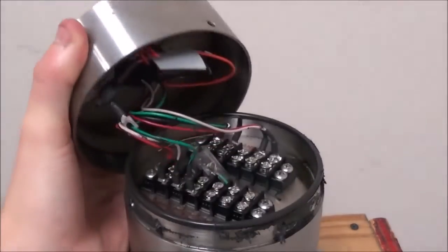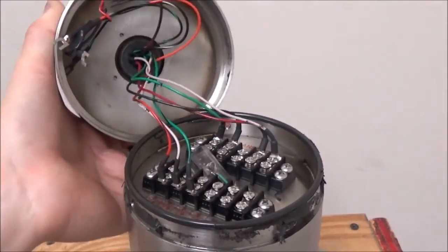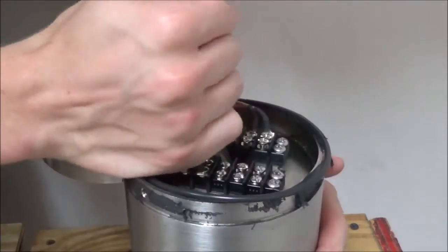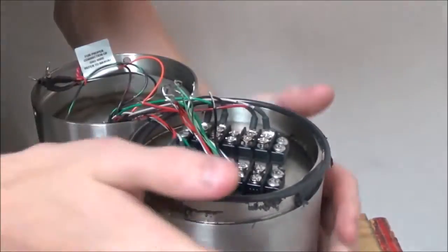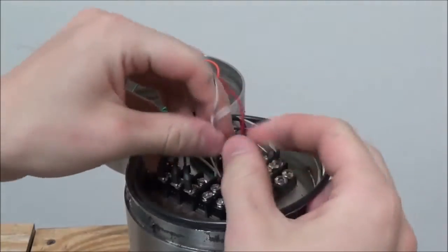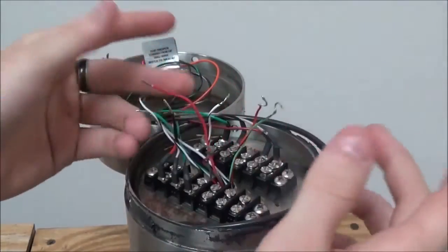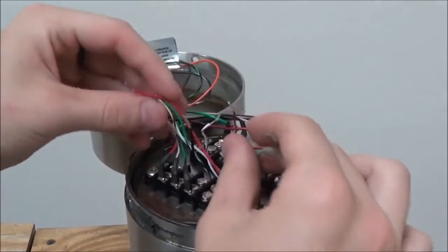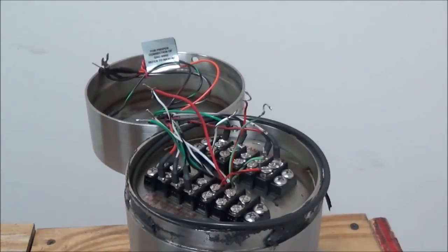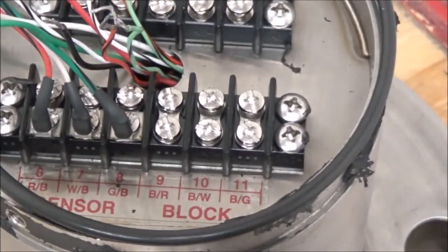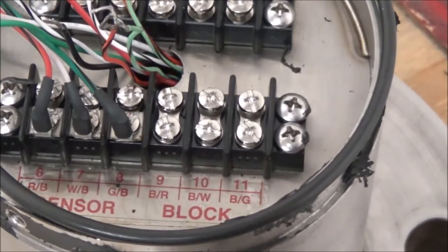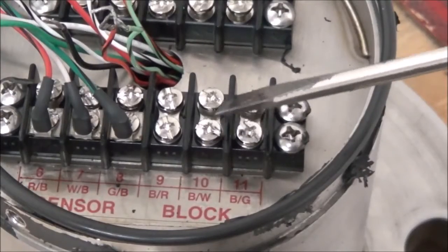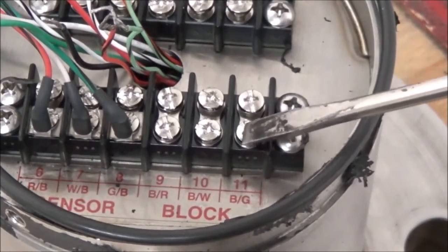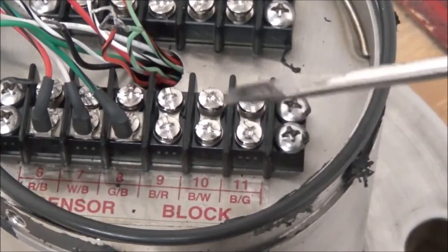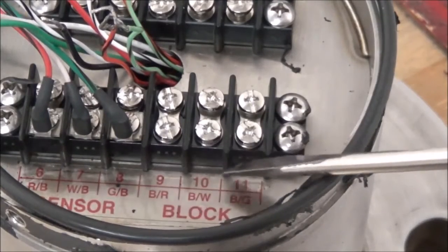Once the sensor block cover has been secured, lift up the transducer block cover and simply pull the plastic tube out of the sensor block hole. Once untangling all the wires, we are now ready to start the rewiring process. You may notice that you now have 11 wires, yet only 8 connected terminals. Well, this is where terminals 9, 10, and 11 come into play, with their corresponding colors of black-red, black-white, and black-green.